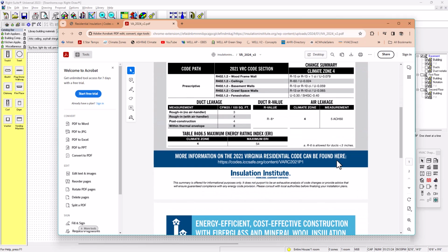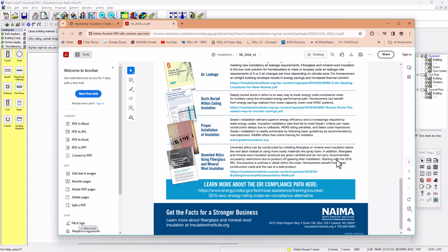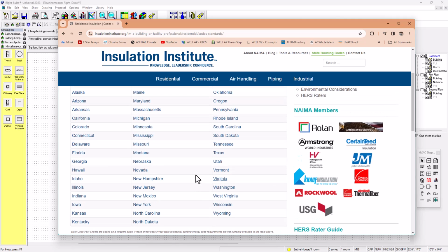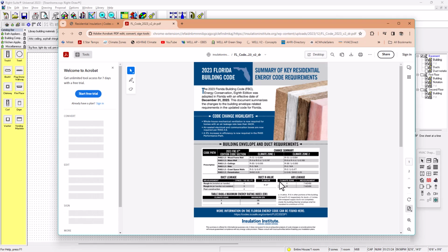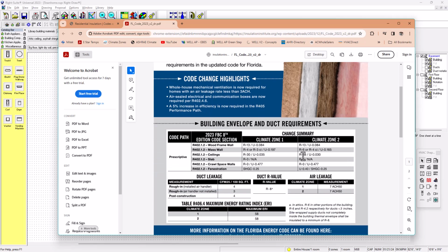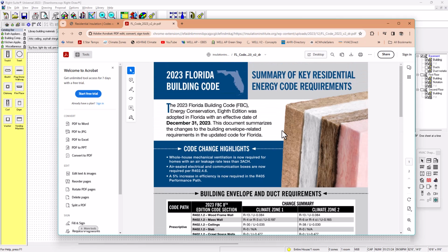And then when you're in Florida, actually, that's a little bit less. Let's be curious very quickly in here. We're going to go to Florida because Florida is another climate zone, like for example Miami. In Florida, maybe you don't need so much insulation based on the code, but let's check. The requirements are, it says for ceilings R38. Then you have your solar heat gain coefficient, your U value, and then your air changes per hour. It's going to be 7 ACH at 50 pascals. So this is actually a very good resource, and I'm going to leave this in the description below.